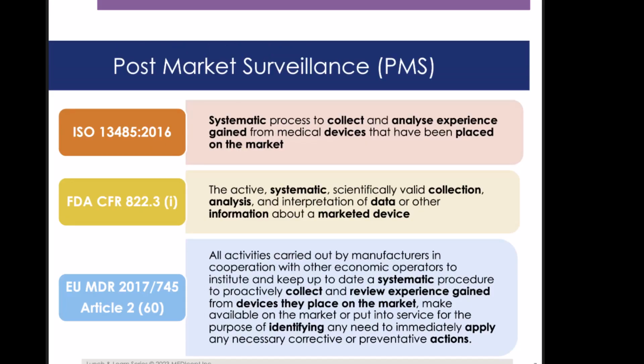So what is post-market surveillance then? The definitions of post-market surveillance from ISO 13485, US FDA, and EU MDR are displayed. Let's highlight the key similarities and intentions of these definitions. Post-market surveillance is the systematic process for collecting and analyzing experience or data of a marketed device. The EU MDR definition adds in the component of identifying and applying actions. Simply put, post-market surveillance is the process to collect and analyze real-world information on the marketed devices. This information is then used to determine what, if any, actions should be taken. It is a tool to monitor and take action to ensure a device continues to be safe and effective.